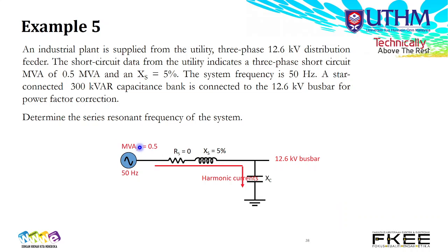which is 3-phase 12.6 kilovolt distribution feeder. The short circuit data from the utility, basically from the generator, of a 3-phase short circuit MVA of 0.5 MVA, and then XS equal to 5%. The system frequency is 50 Hz. A star connected 300 kVAR capacitor bank is connected to the 12.6 kilovolt busbar for the power factor correction.